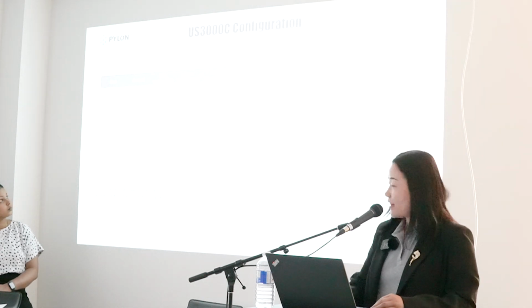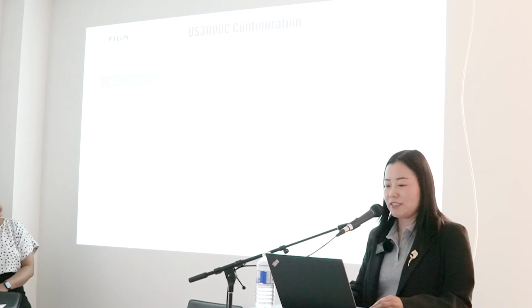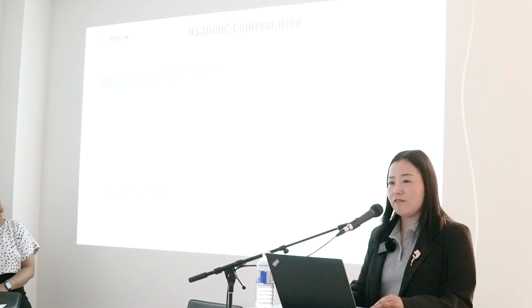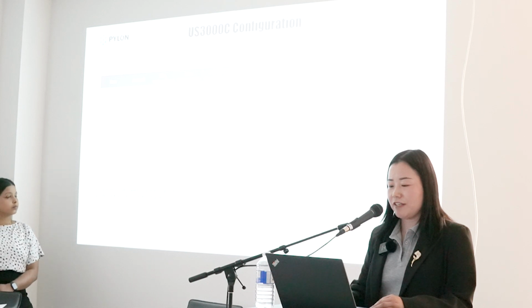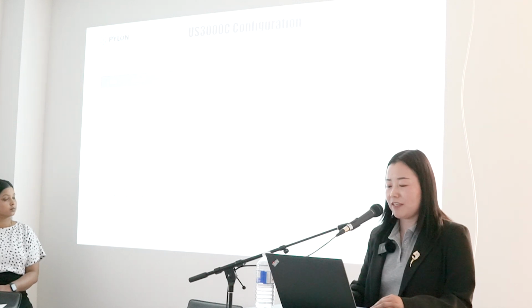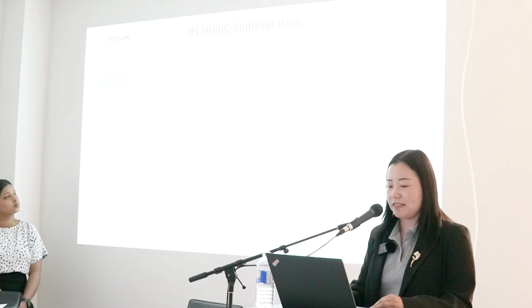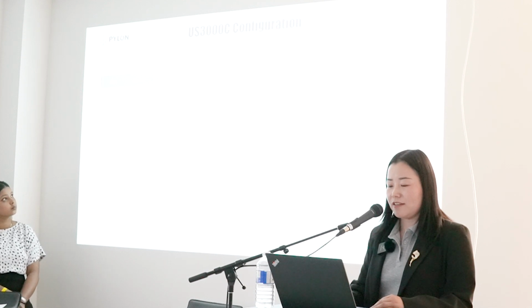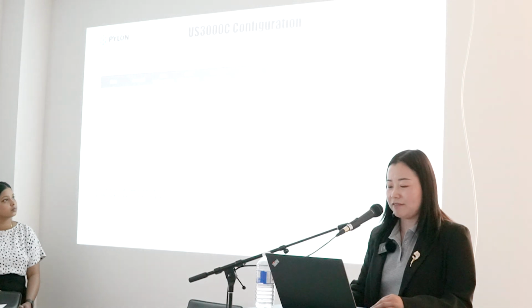Here is the US-3000C configuration in one string. The voltage range is from 44.5 to 53.5 volts. Nominal capacity of single battery module is 3.55 kilowatt hour. Usable power is nominal capacity times the DOD, which is 95%. And the rated power is under 37 amp, 48 volts. Max power for 60 seconds is under 74 amp. Peak power for 15 seconds is under 90 amp. Rated max peak power is based on ideal operation temperature from 10 to 45 degrees.